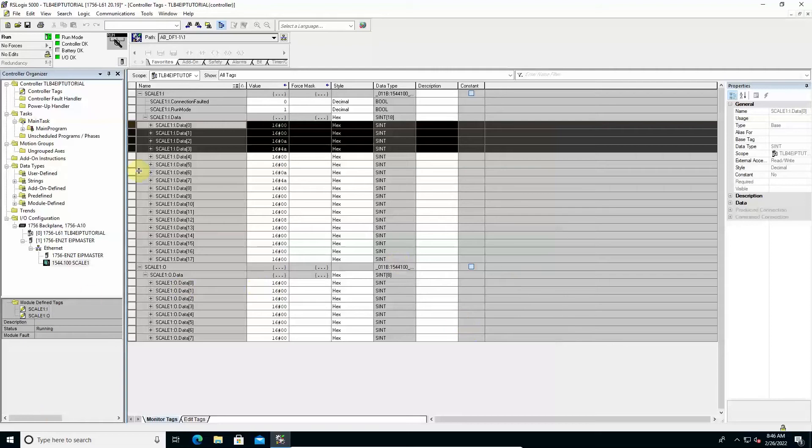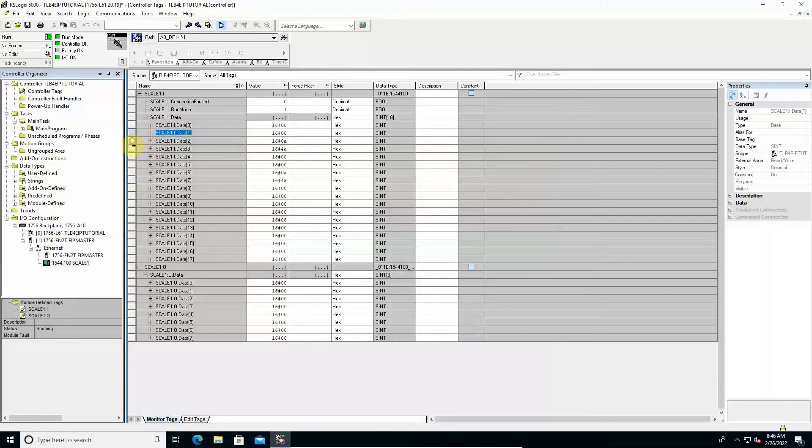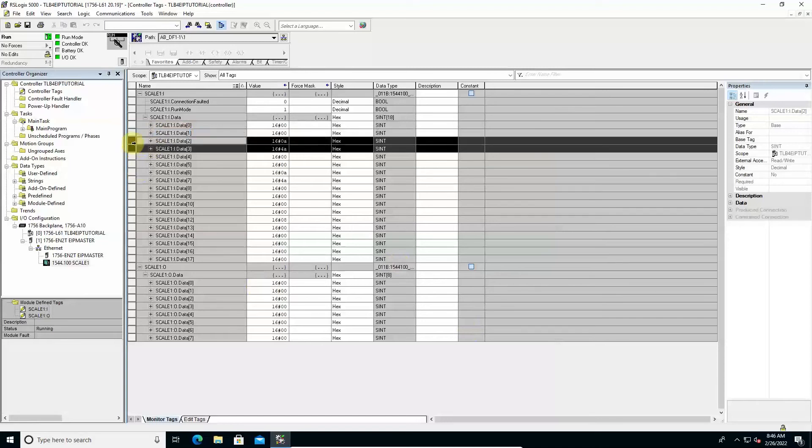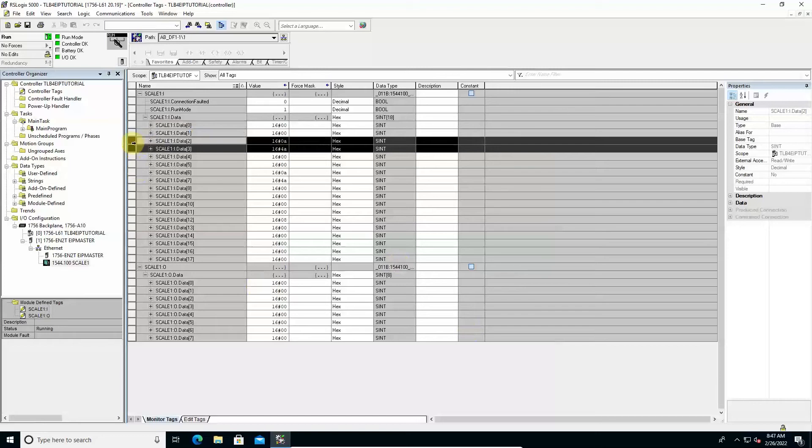In this way, the bytes of lower value are the last. The choice among Little or Big Endian notations is often related to the automation system and used software libraries characteristics. The same notation used for weight values, Big or Little Endian, is used for all the published values with a multiple byte size, for example, status register or exchange register.